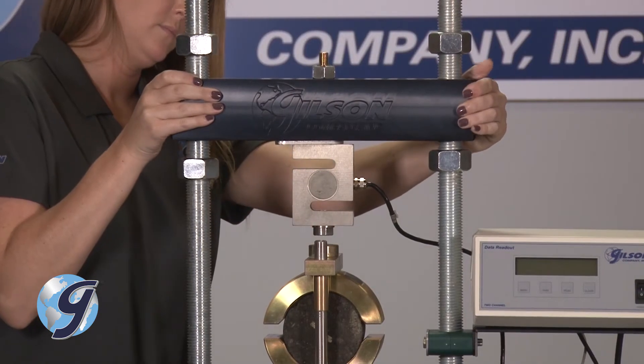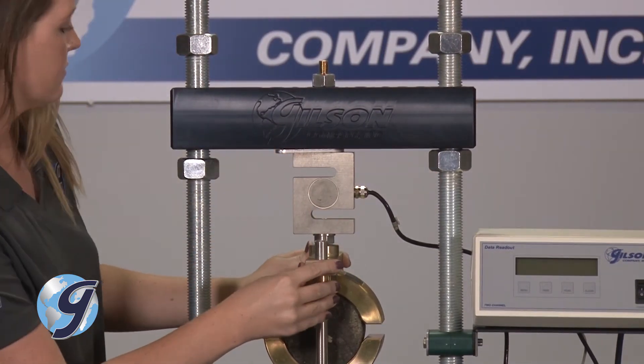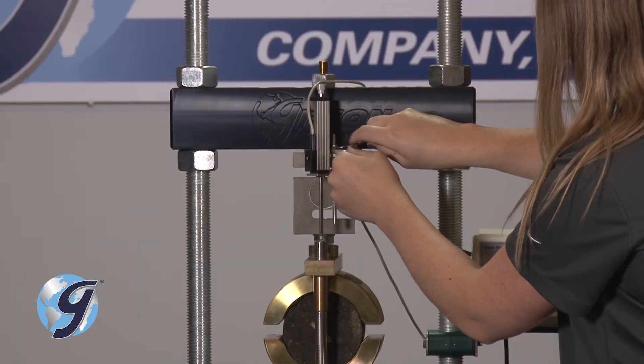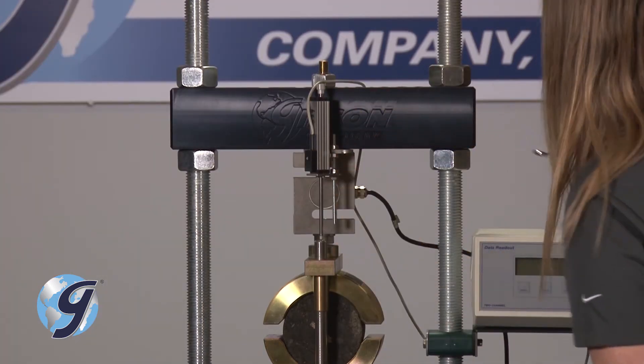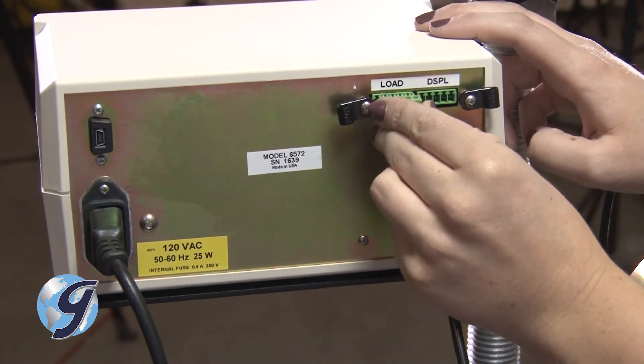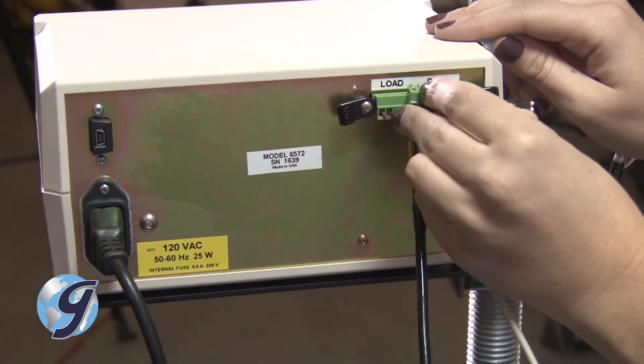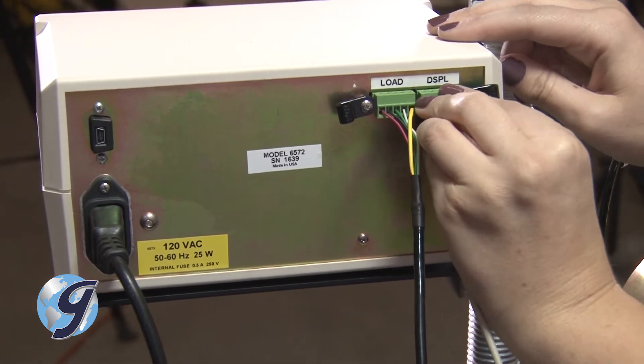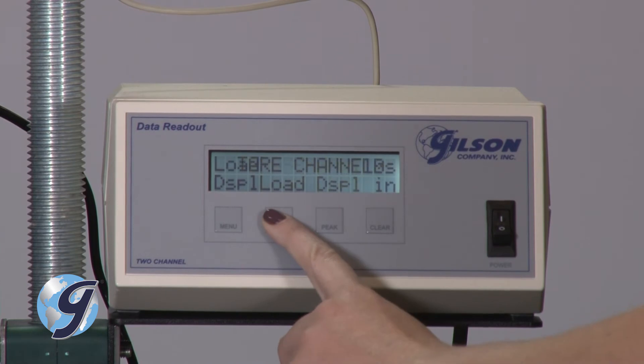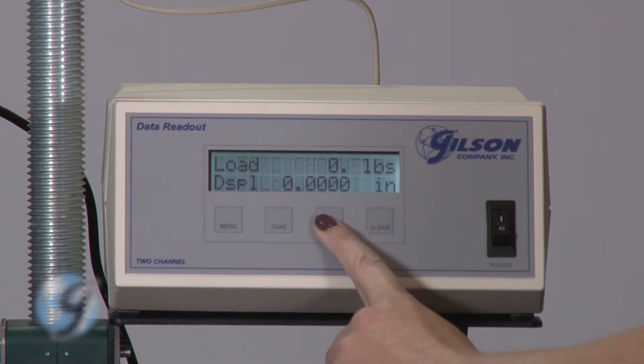Now, adjust the height of the crosshead to the center point of the fixture. Next, attach the LVDT to the indicator bracket and then seat the LVDT on the vertical guide rod of the Marshall breaking head fixture. The load cell and LVDT are then connected to the data readout to display the load and displacement during a test. Tare both the load cell and the LVDT. Now, you are ready to begin the test.